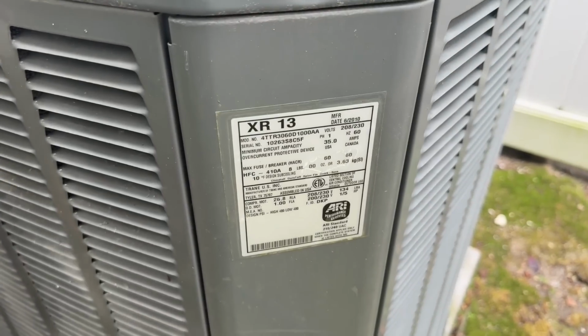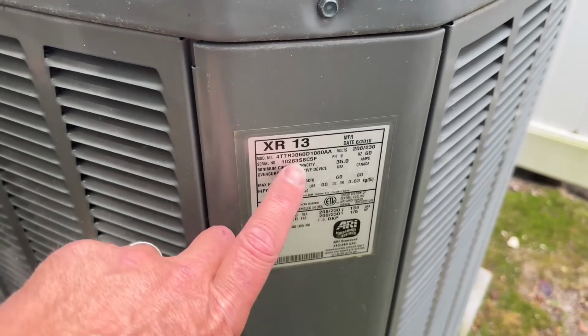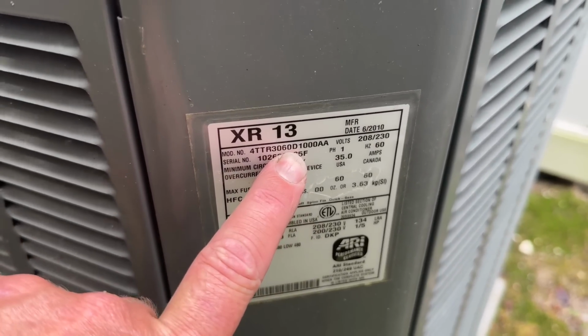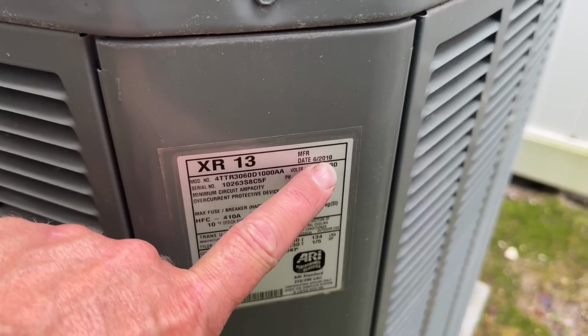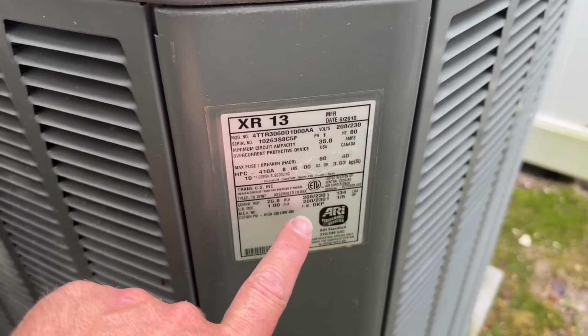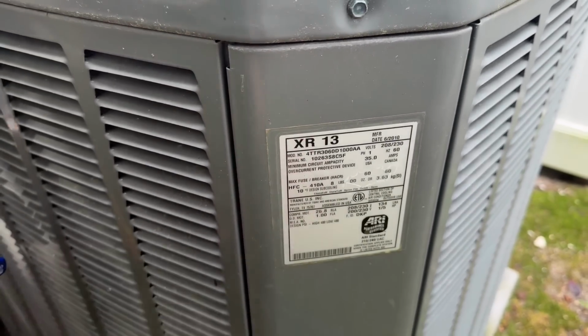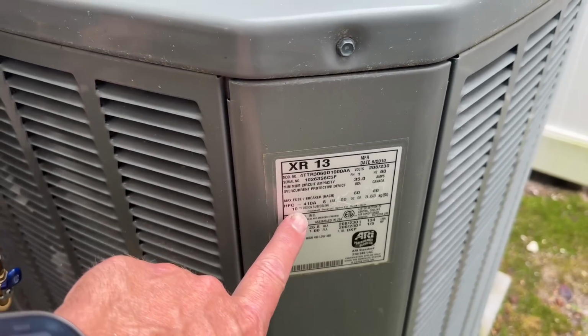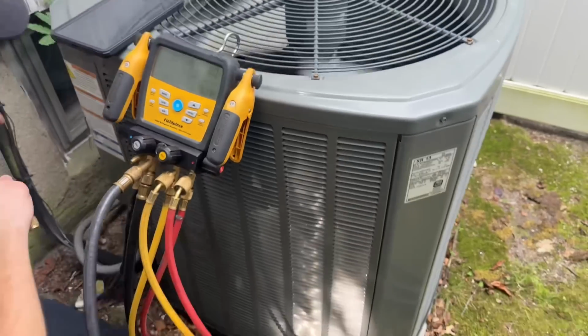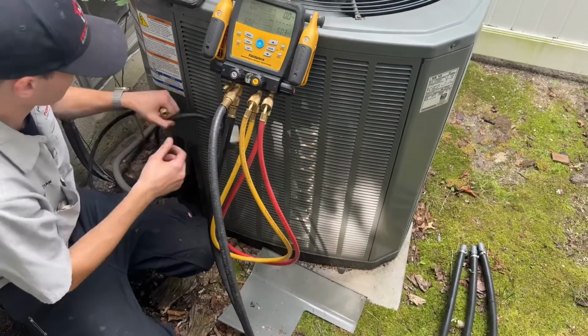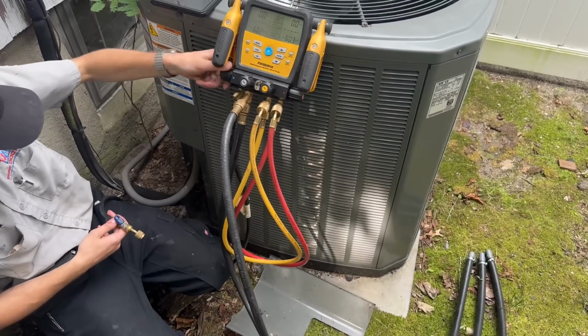All right, we got this Trane XR13. That 60 means it's 5 tons. Manufacture date of June 2010. And we are 410A. 10 degrees of subcooling we're looking for. And watch what we get once we hook up our refrigeration manifold to the system.